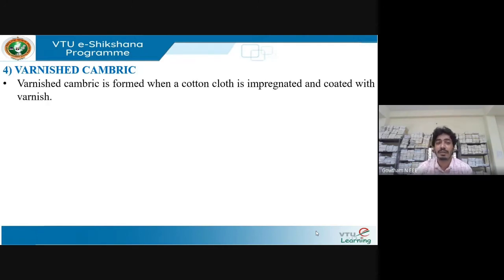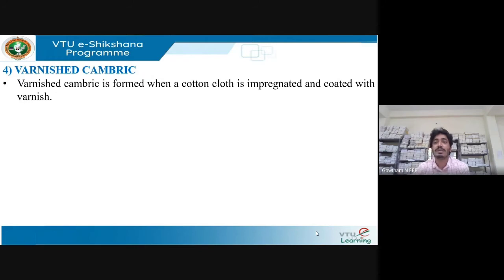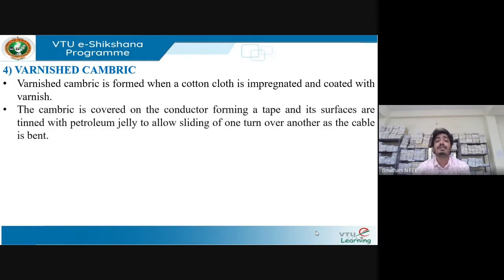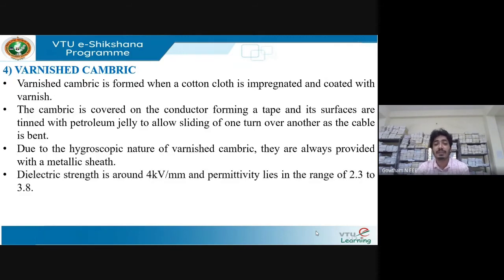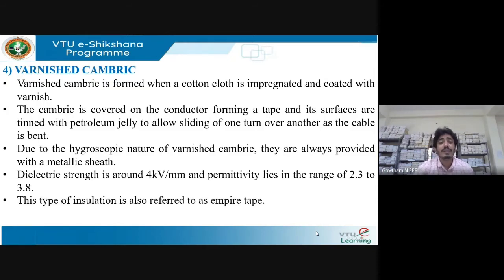Varnished cambric is a cotton cloth impregnated with varnish. The cambric is covered on a conductor forming a tape, and its surfaces are coated with petroleum jelly to avoid sliding of one turn over the other as the cable is bent. Cotton cloth is hygroscopic. The dielectric strength of varnished cambric is around 4 kV per millimeter and its permittivity lies in the range of 2.3 to 3.8. It is also called empire tape and is one of the important insulating materials used in cables.